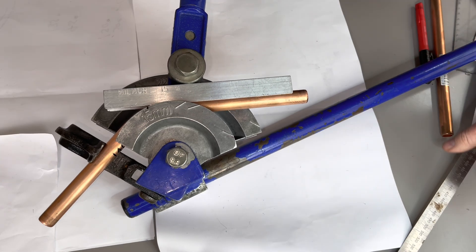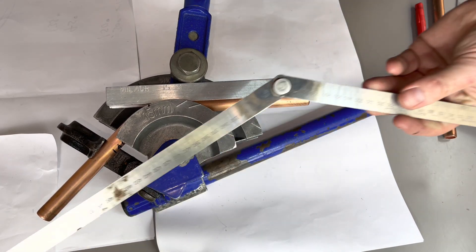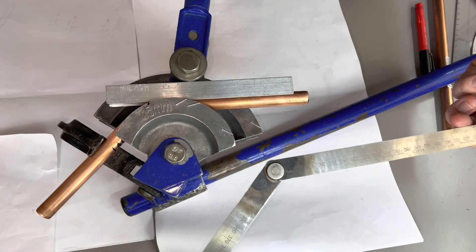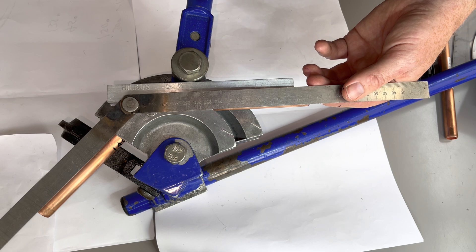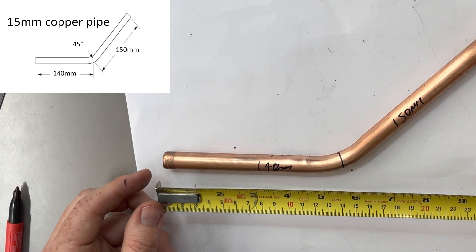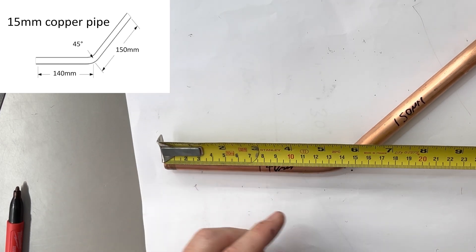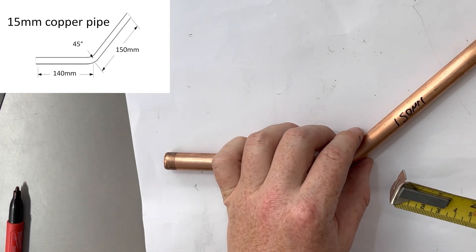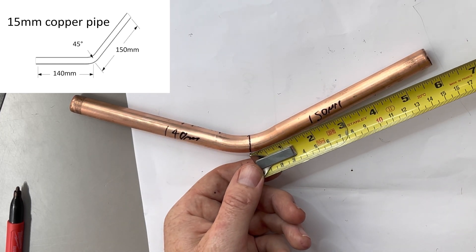Okay, we always double check the accuracy of our pipe bender by putting a folding ruler on the pipe to check the accuracy. Okay, so let's then check our measurements to the specification. So 140 mil to the center of the bend, then the other side needs to be 150 mil.